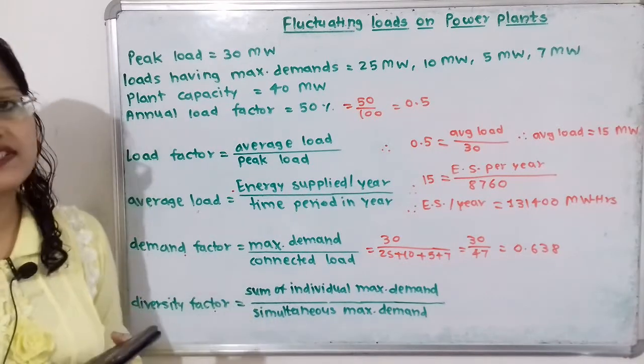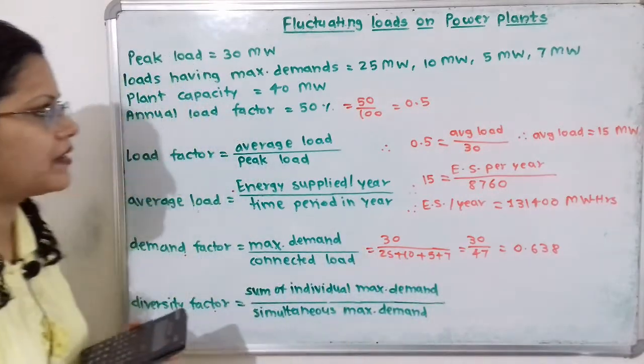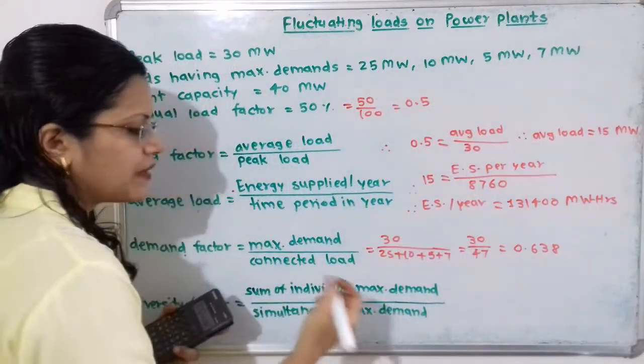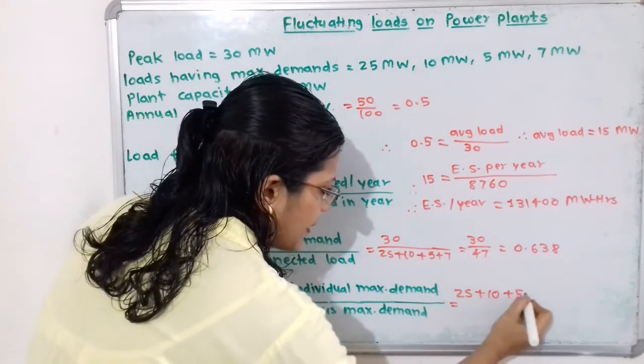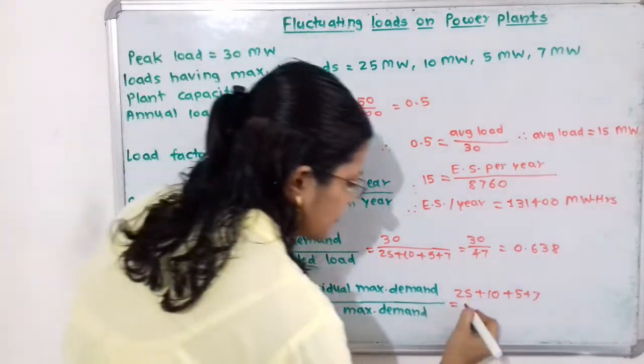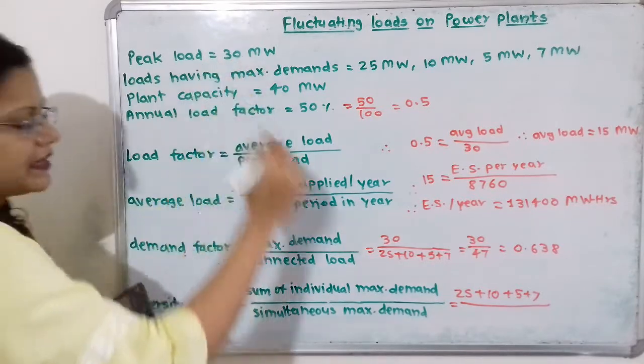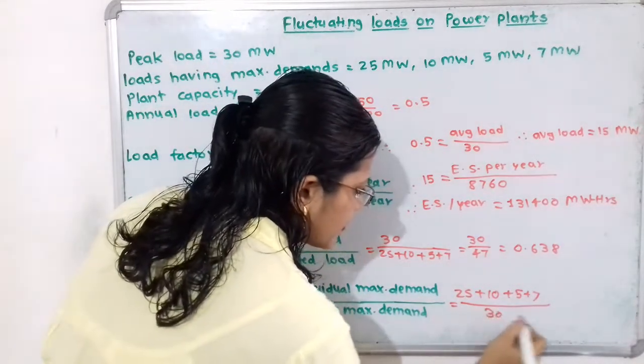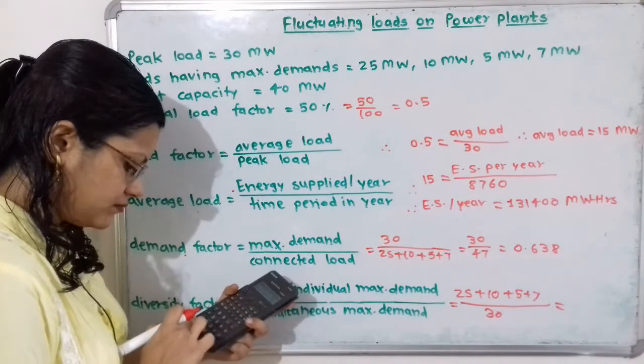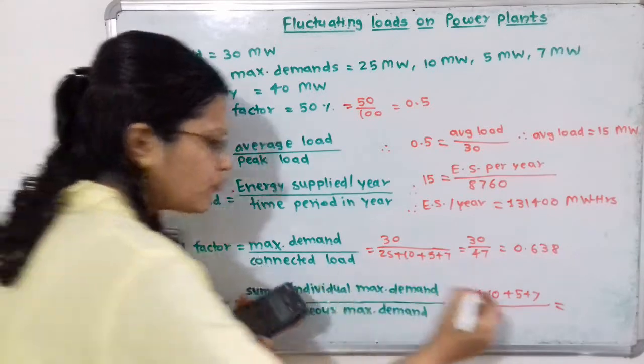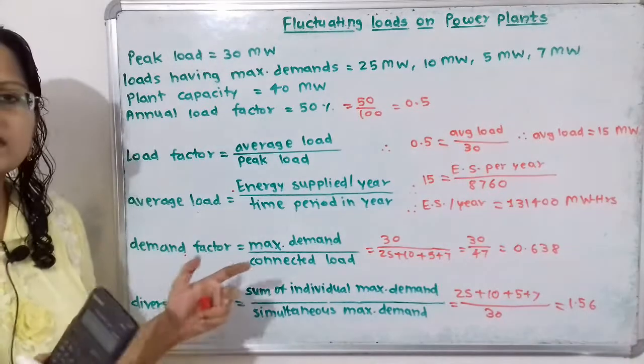Now we will calculate the diversity factor. Diversity factor equals sum of individual maximum demands divided by simultaneous maximum demand. Sum of individual maximum demands is 25 plus 10 plus 5 plus 7, which equals 47. Simultaneous maximum demand is the peak load, that is 30 MW. So diversity factor equals 47 divided by 30, which equals 1.56. There is no unit. So these are the answers.